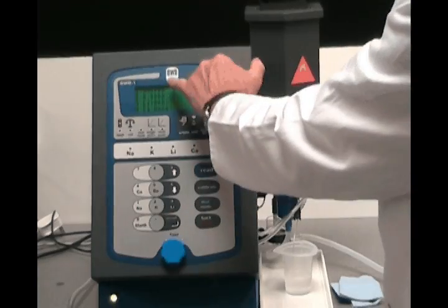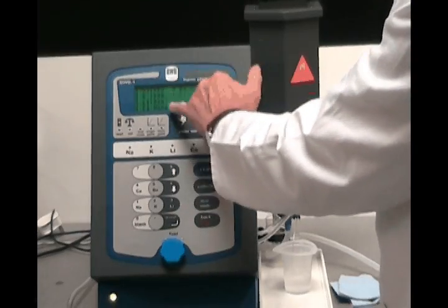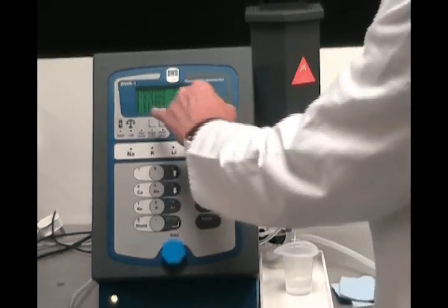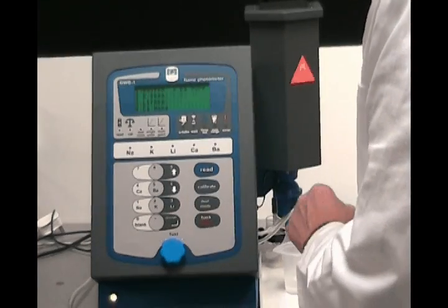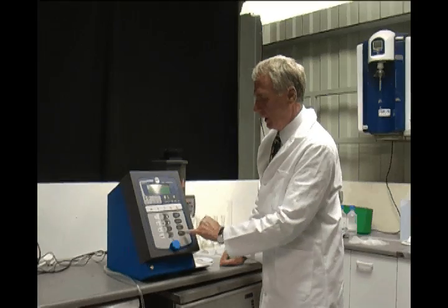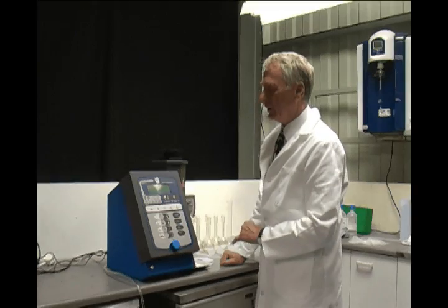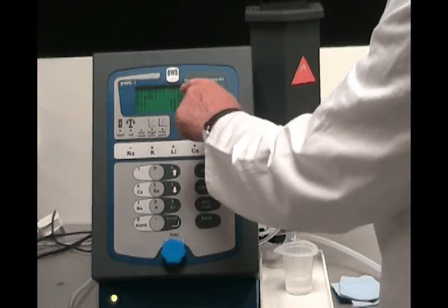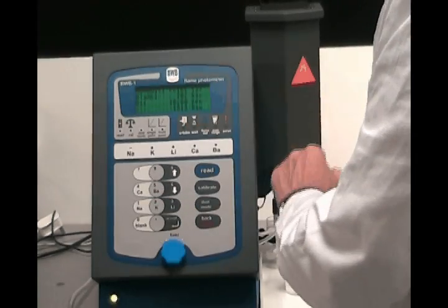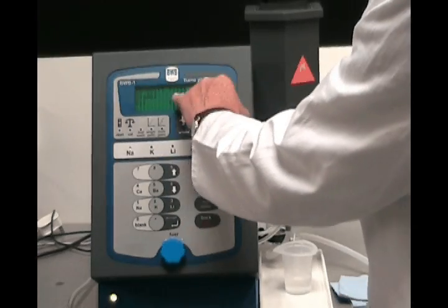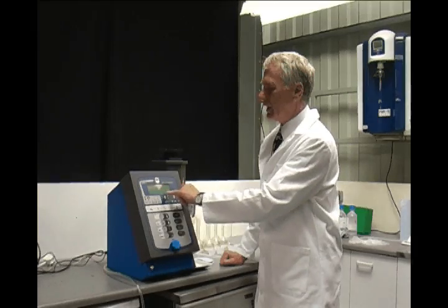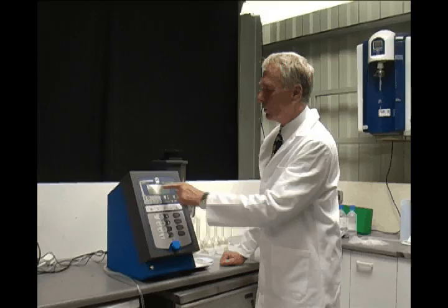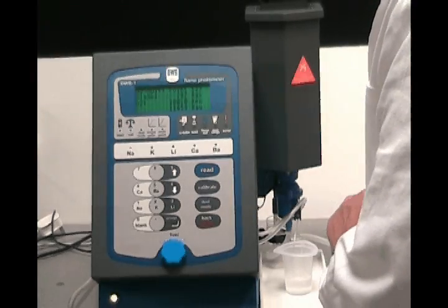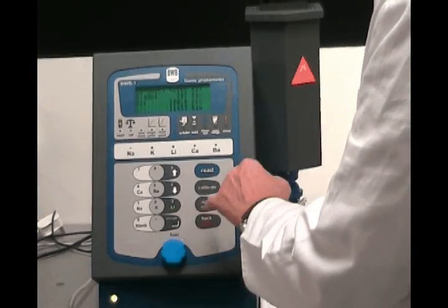It's telling us that sodium, potassium and lithium are all calibrated in ppm. There is no calibration for calcium or barium. If we press accept to look at the sodium calibration, it's telling us it's a multi-point, 2-point calibration and giving us readings for the blank reading, the 10 ppm, and if I scroll down it'll give me the value for the 100 ppm reading as well.